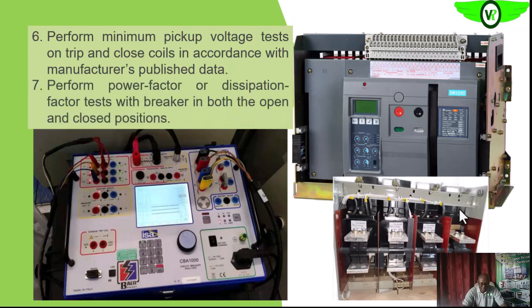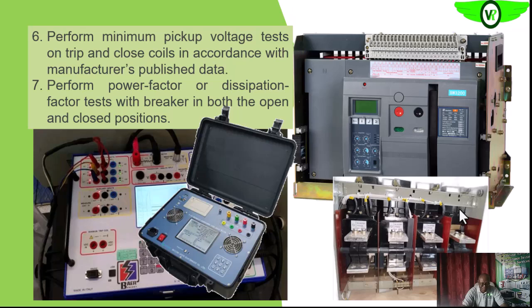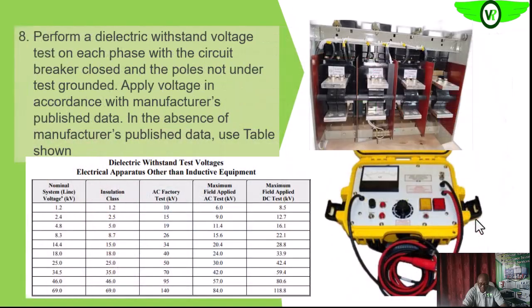We also want to perform the power factor test, or dissipation factor test, using the power factor meters. That is basically testing the insulation between the phases and ground for high voltage equipment. This is more effective for determining the integrity of the insulation than the ordinary insulation resistance tests. We also want to perform the dielectric withstand test, and if we do not have something recommended by the manufacturer or already in place in our facility, we can use this as a guide.